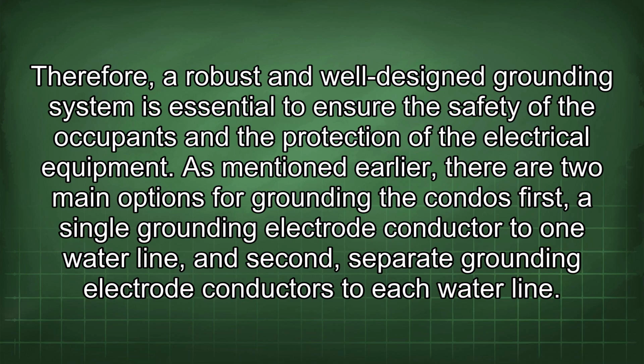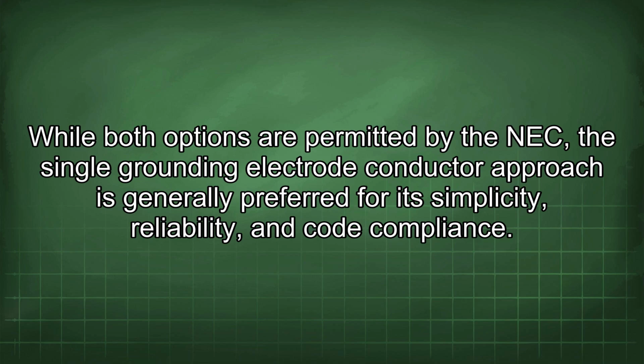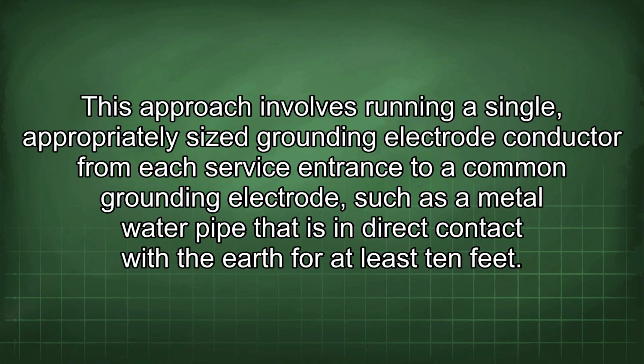As mentioned earlier, there are two main options for grounding the condos. First, a single grounding electrode conductor to one water line, and second, separate grounding electrode conductors to each water line. While both options are permitted by the NEC, the single grounding electrode conductor approach is generally preferred for its simplicity, reliability, and code compliance.